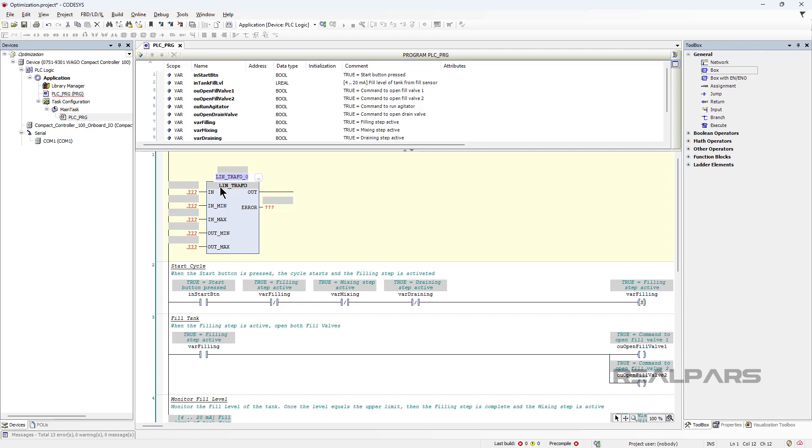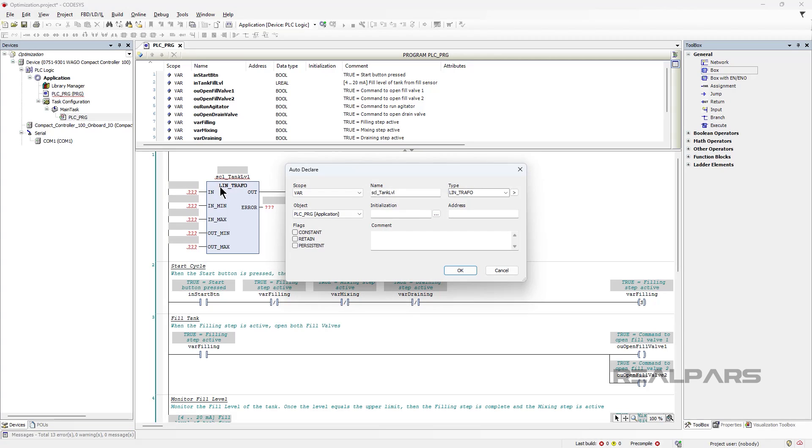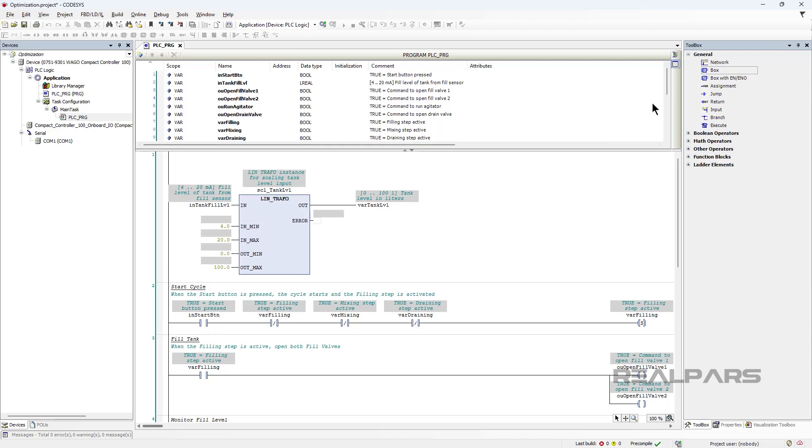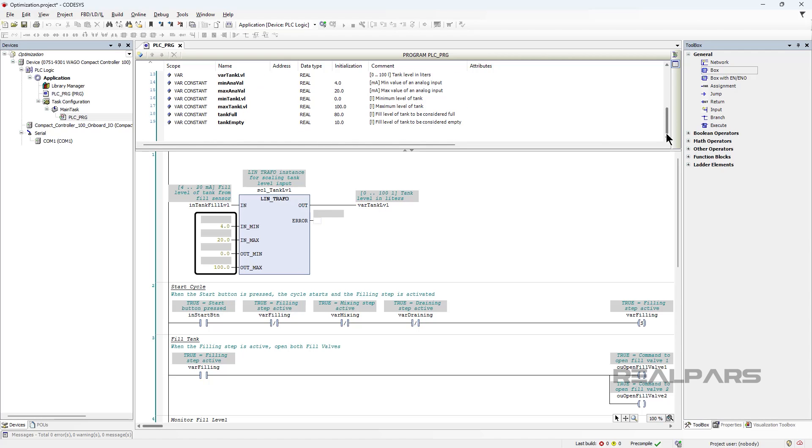To make it easier to understand what numbers in our programs represent, we can scale values from raw data values like 4 to 20 milliamps to engineering units like 0 to 100 liters as shown here. This is better, but we can still make this program more clear by removing hard-coded numbers.